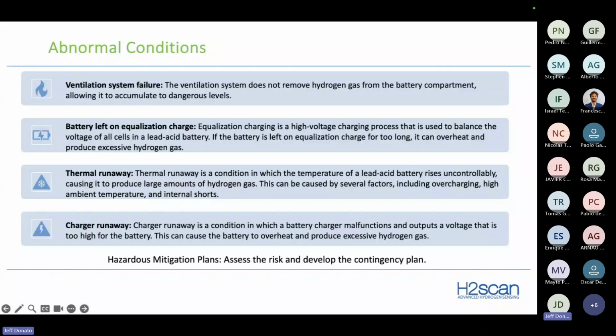Some of the abnormal conditions I'll bring to your attention that we need to consider. It's not just normal operation that we have to take into account when designing these systems. One thing that I've seen a lot more enforcement around is ventilation system failure. A lot of times the hydrogen mitigation or detection systems, whether that be just a constant running fan, or something even more advanced, like maybe a fan on a timer, didn't really allow for the mechanical failure of that system. So what happens if the fan fails? And that's something that a lot of authorities are asking questions about today.